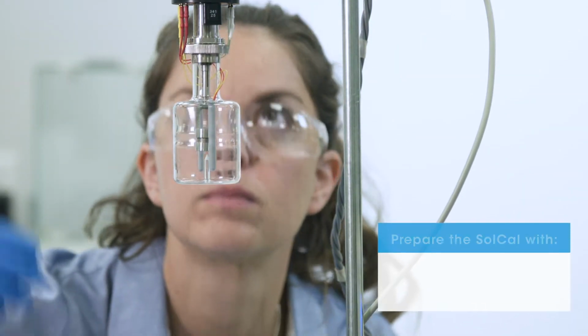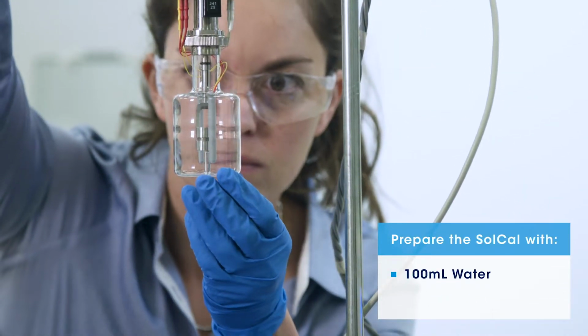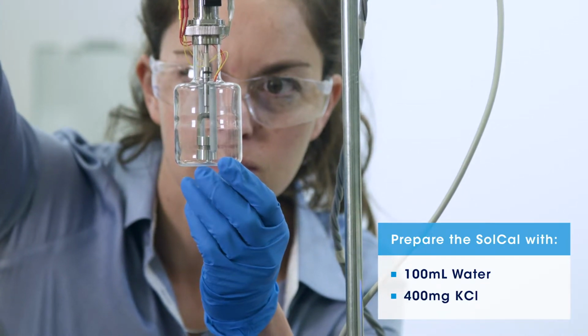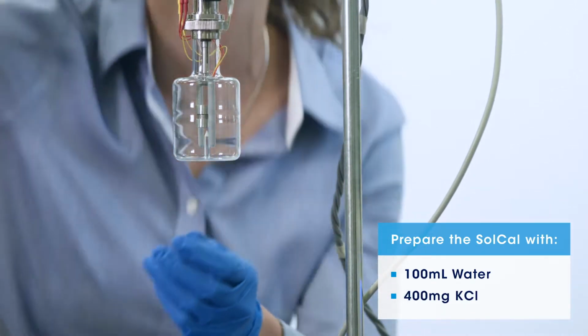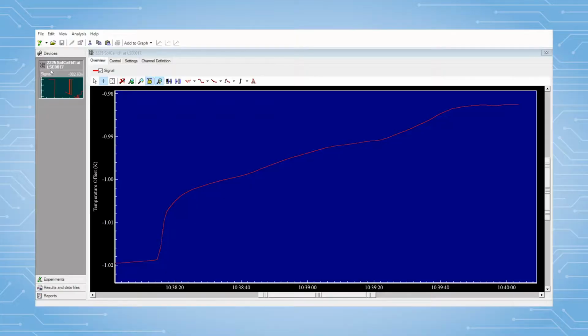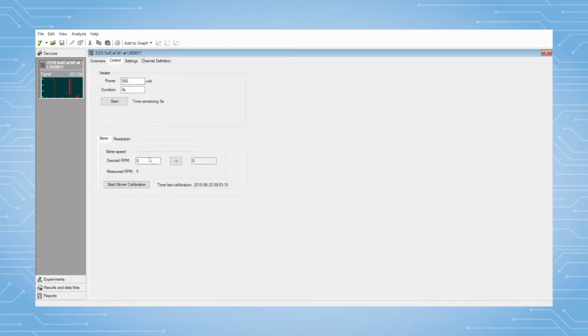Start by preparing the SolCal with exactly 100 ml water and about 400 mg of pure and dry potassium chloride. Start the stir in the TAM Assistant SolCal device. A recommended stirring rate is 500 rpm.